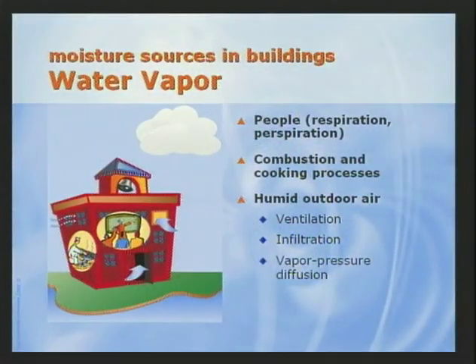Make every effort to thoroughly dry carpets within 24 hours. Finally, common areas where unplanned condensation can occur are door and window frames, on the underside of wall coverings, and on cold pipes, ducts, or equipment. Water vapor is generated inside the building, or it can enter from outdoors. Indoor sources include respiration or perspiration from people, evaporation from open water surfaces such as pools, and combustion or cooking processes. Outdoor sources include humid outdoor air that is brought in by the ventilation system, humid air that infiltrates through cracks and other openings in the building envelope, which includes doors and windows, and diffusion through the envelope.